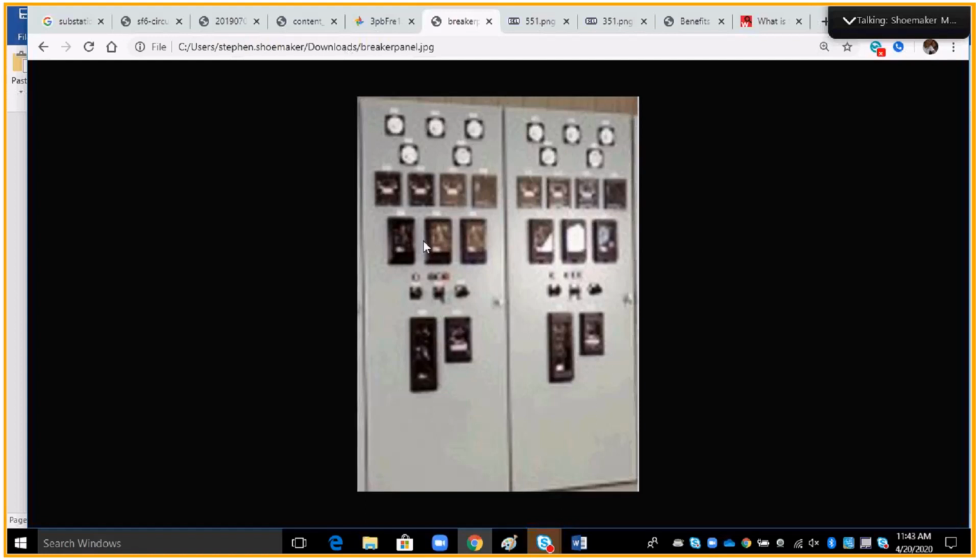I know the Santee Cooper system is one instantaneous and two timed, so I'm counting on off real quick. Or excuse me, off on real quick. Then all of a sudden off, and it's waiting. I'm counting 1 1000, 2 1000, 3 1000. Then the power comes on. Then the power goes off. I'm thinking 1 1000, 2 1000, 3 1000. If the power comes back on and stays on, I'm happy.